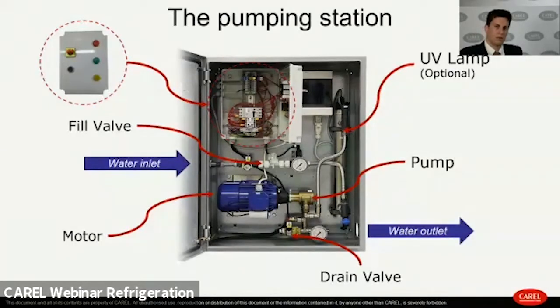One important point that I would like to underline is the hygiene. As you can see in the picture, on the bottom, there is a drain valve installed. The drain valve is a solenoid valve that can be opened through the electrical panel whenever the system is not asked to spray water anymore. So in this way, we can drain water out from the circuit, and we are sure that no water stagnation can be present in the system.